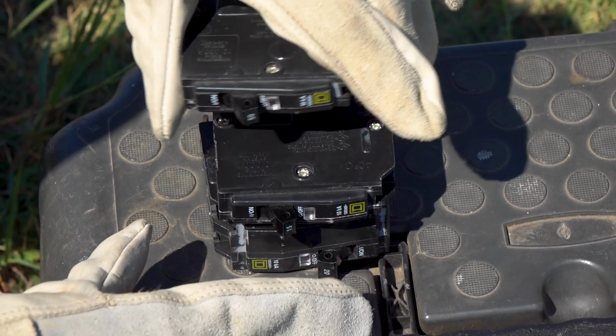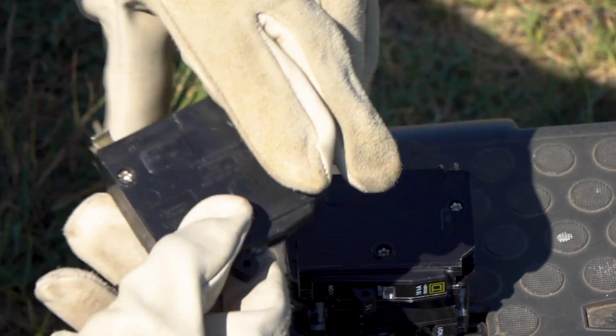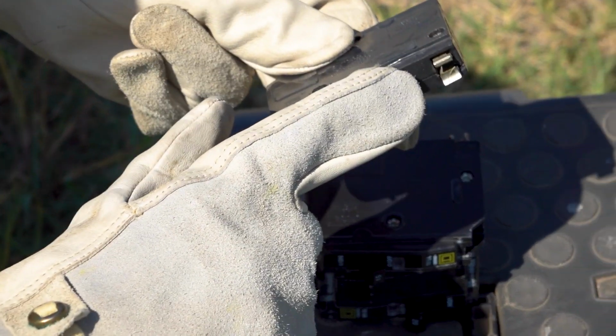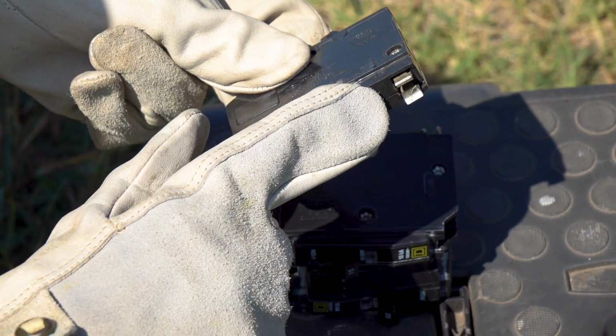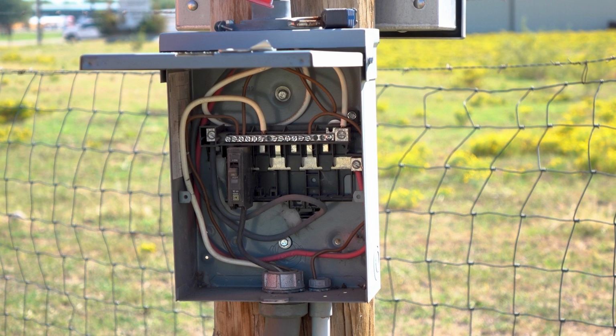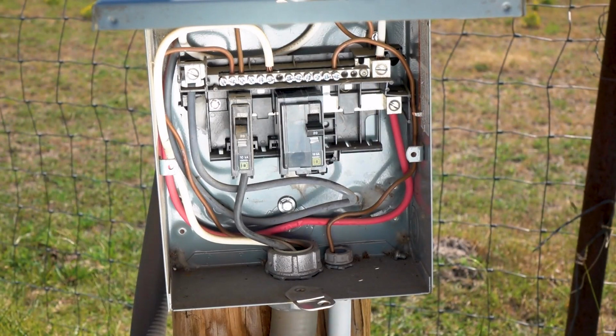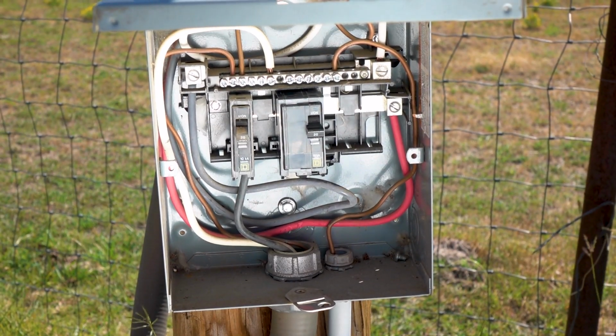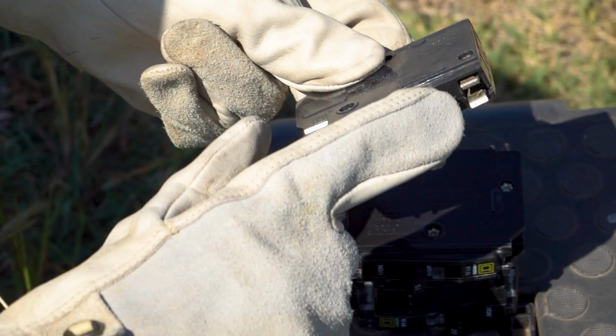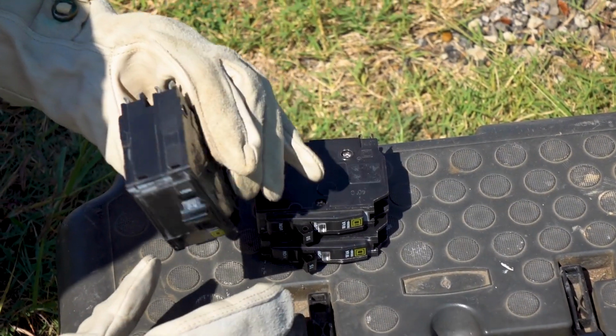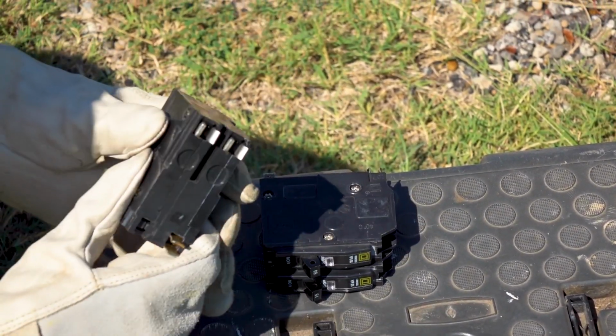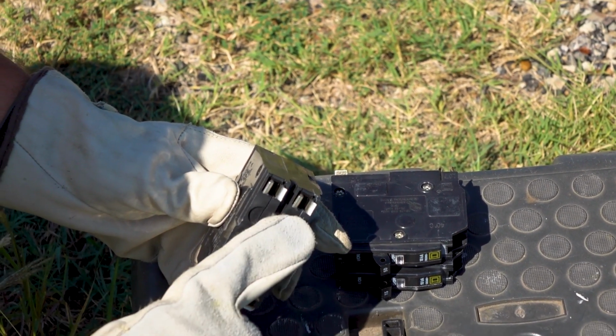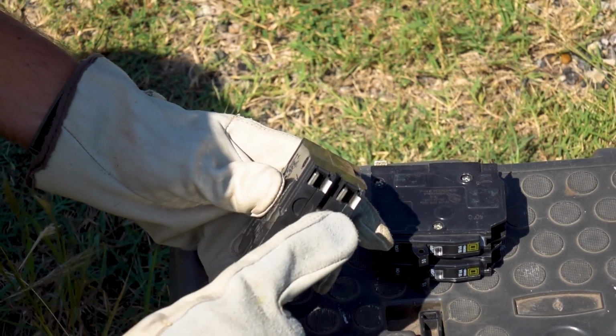spaces. When a Type T service provides power for a signal intersection, the 120-volt traffic signal control cabinet will use 1 space in the service for a single pole breaker. When the signal intersection has a light fixture operating at 240 volts, they will use a 2-pole breaker, which takes up 2 spaces. A single pole breaker will turn power on and off to 1 conductor, and a 2-pole breaker will turn power on and off to 2 conductors. Breakers also protect the conductors of their circuits from being damaged by short circuits, ground faults, and overloads.